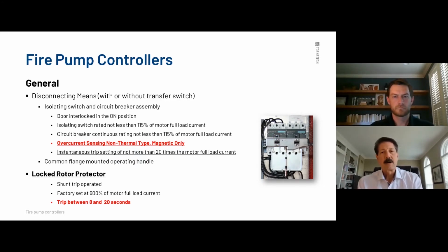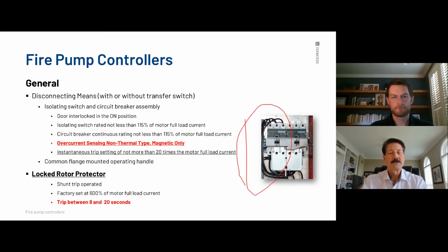The breakers themselves are operated by a flange-mounted operator on-off switch, and the circuit breaker on the left side here again is magnetic. That offers locked rotor protection. It is shunt trip operated, and that's obviously how, when we're sensing a locked rotor situation, which is set at 600% of full load amperage, it will trip offline with an 8 to 20 second range. And that's what happens basically. It will energize that shunt trip device and trip the breaker offline.